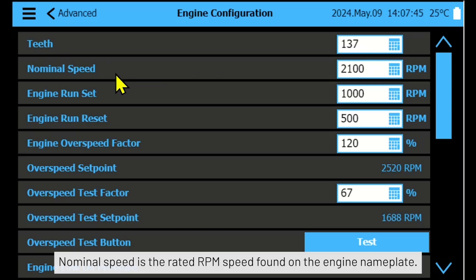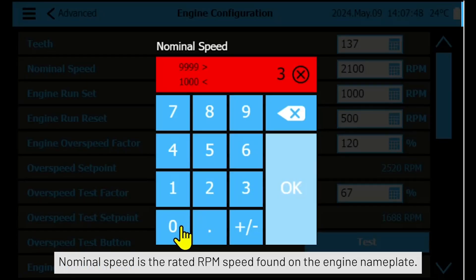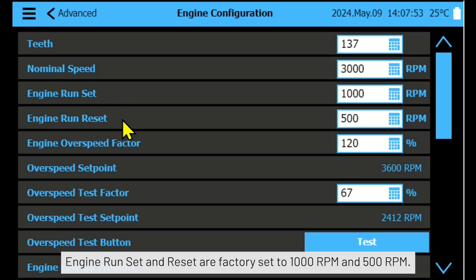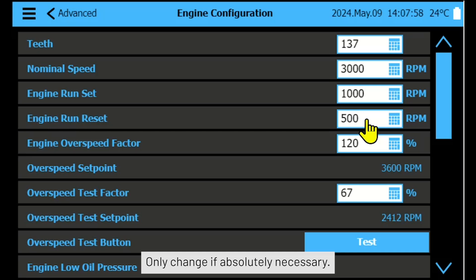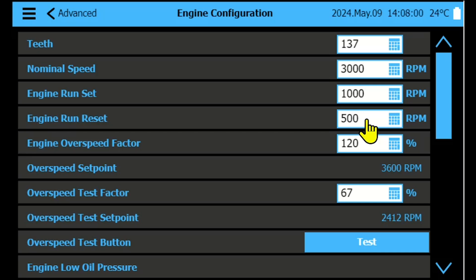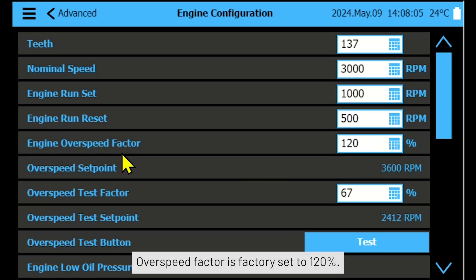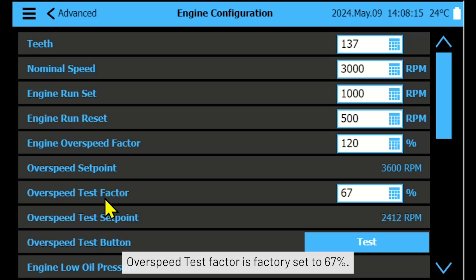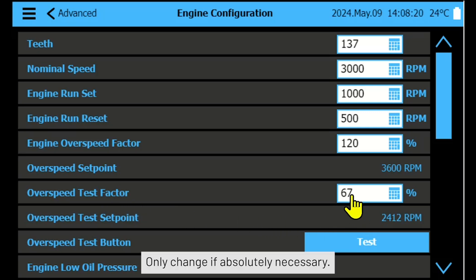Nominal speed is the rated RPM speed found on the engine nameplate. Engine run set and reset are factory set to 1000 RPM and 500 RPM — only change if absolutely necessary. Over speed factor is factory set to 120% — only change if absolutely necessary. Over speed test factor is factory set to 67% — only change if absolutely necessary.